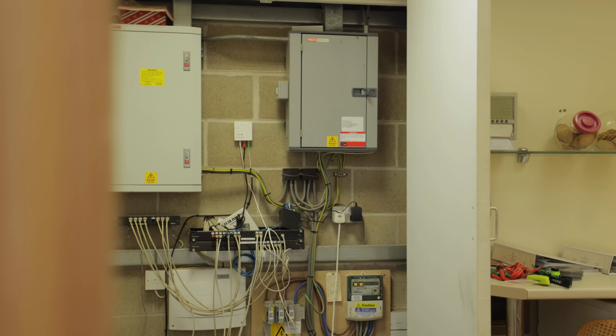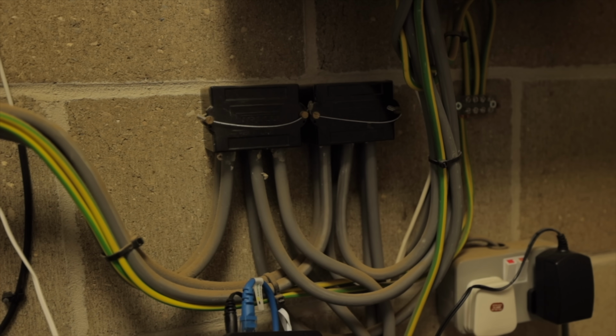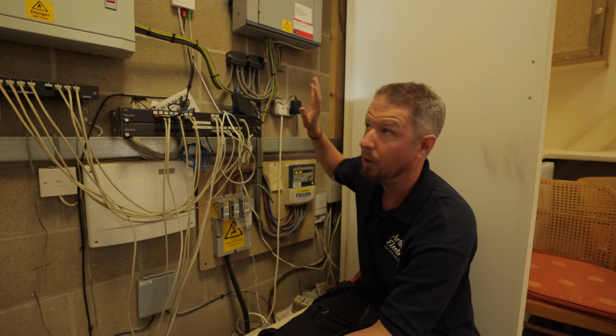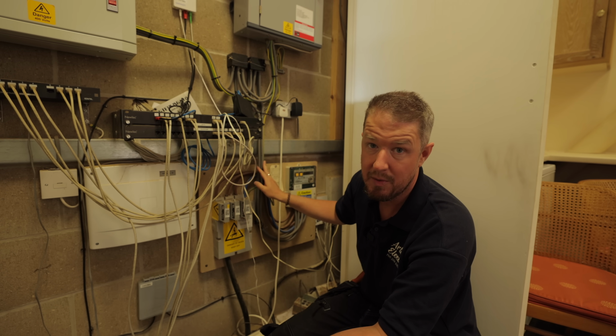What we do is systematically work our way through the installation, follow the tails, record the sizes of all the cables, check the main bonding, and then go through circuit by circuit and check all of the circuits within these 2 distribution boards.